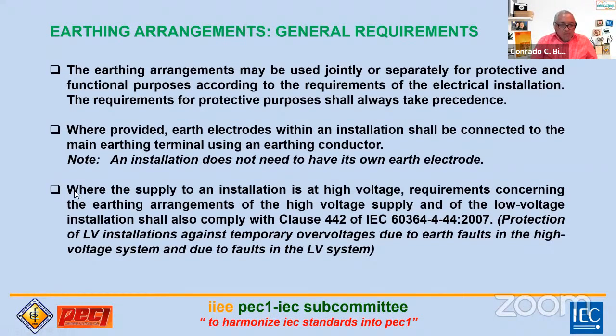This is also important: where the supply of an installation is at high voltage, requirements concerning the earthing arrangements of the high voltage supply and of the low voltage installation shall also comply. This is another part of the standard, part 4.44. One of the important things to address is temporary overvoltages due to earth faults in the high voltage system and due to faults. So at the utility, if a ground fault occurs in the system, what's the effect on the low voltage side? Problems often occur because of this. Of course, you can mitigate these temporary overvoltages.